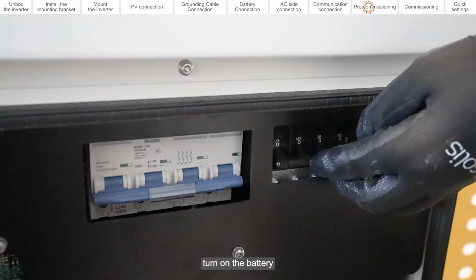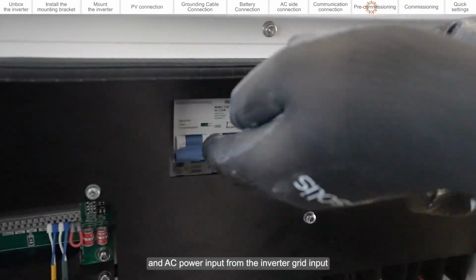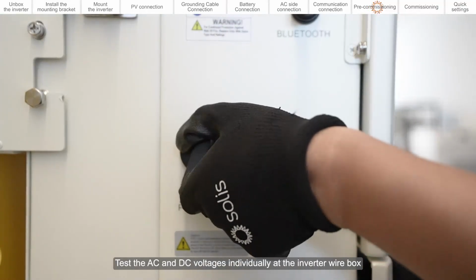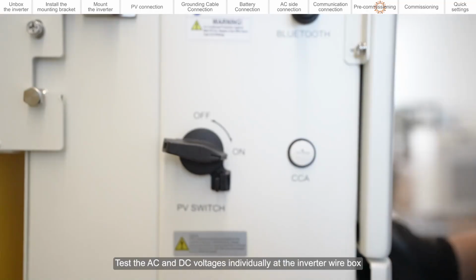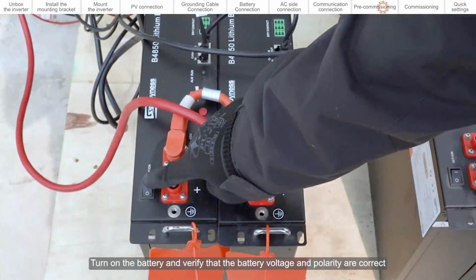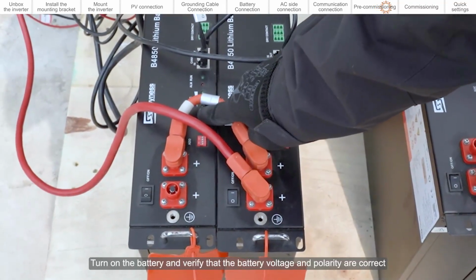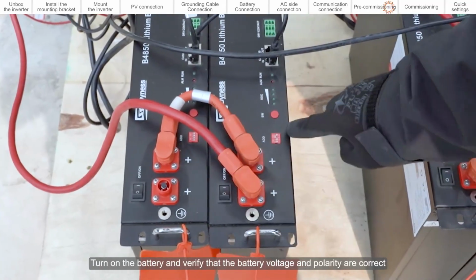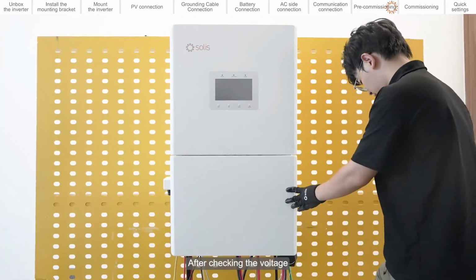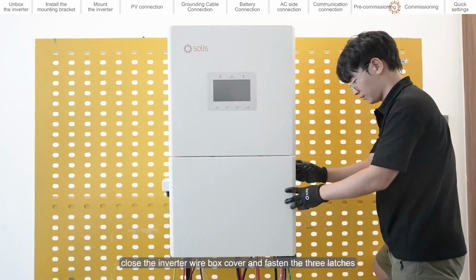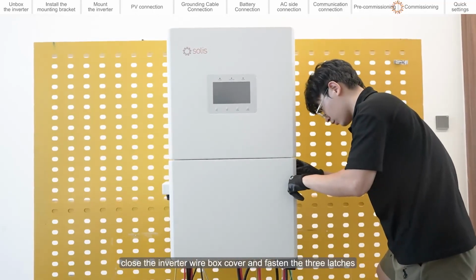Then, turn on the battery, PV switch, and AC power input from the inverter grid input. Test the AC and DC voltages individually at the inverter wire box. Turn on the battery and verify that the battery voltage and polarity are correct. After checking the voltage, close the inverter wire box cover and fasten the 3 latches.